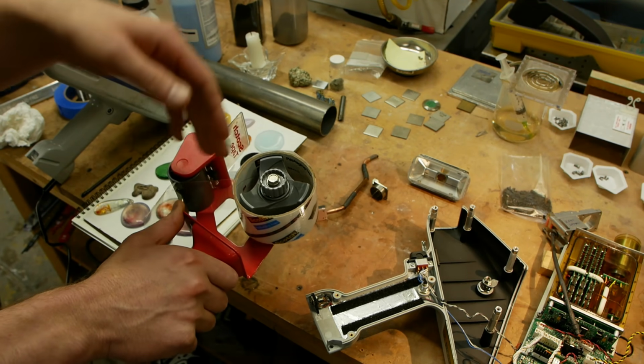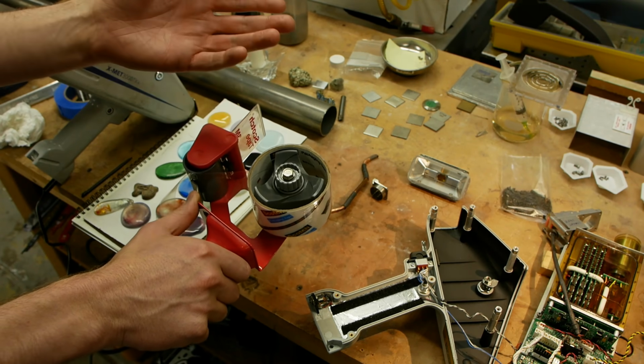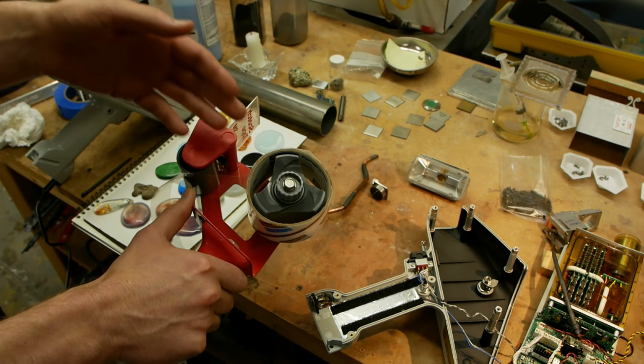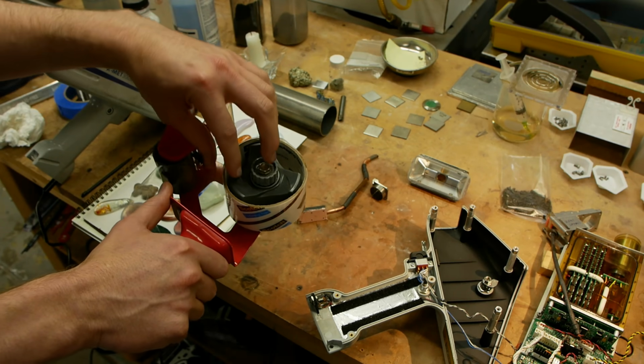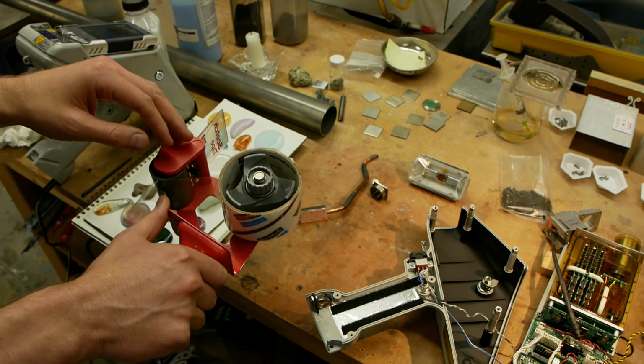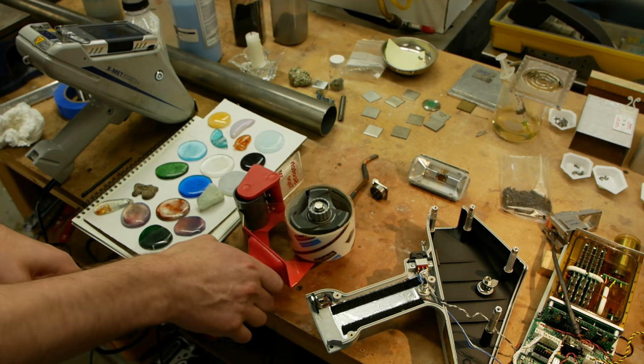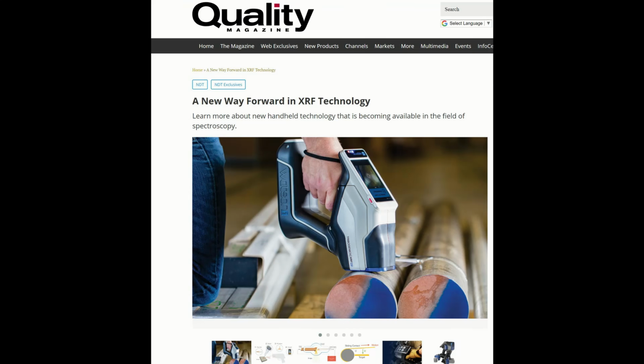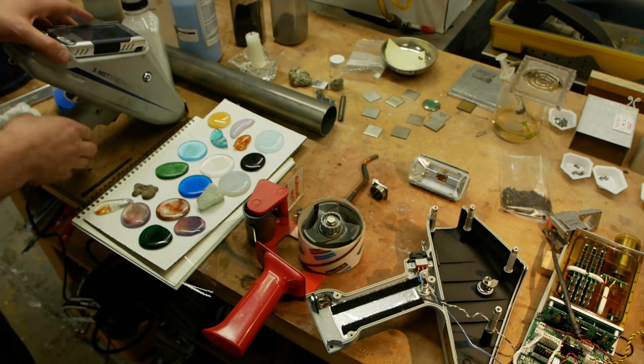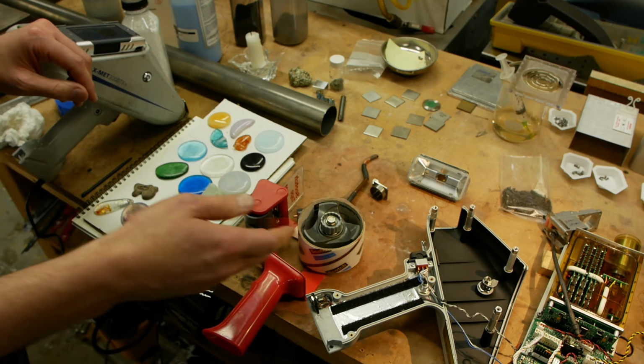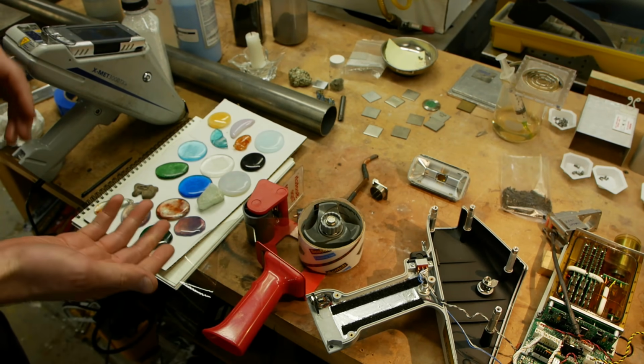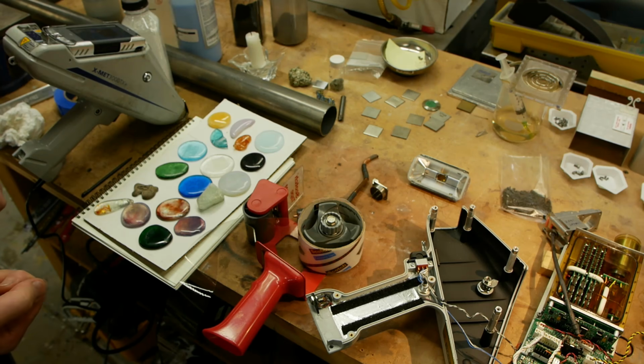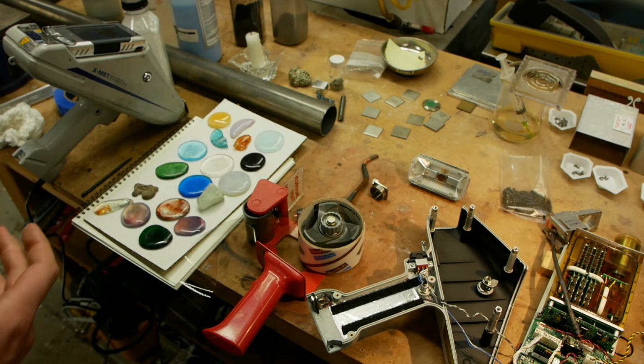The charge slams into the other side and equalizes itself out. On the order of 50 kilovolts can be built up this way. And you end up with X-rays because now you've got a 50 kilovolt charge with some electrons flying off and making the X-rays for you. So the researchers that found this principle started a company to produce XRF guns based on this principle. And as we saw, the power supply is pretty complicated. So if you avoid the X-ray tube and the power supply, you might be able to build the guns for less money. This company existed, and I don't think they went out of business, but they're kind of ceasing operations or something. But you can still find the guns on eBay.